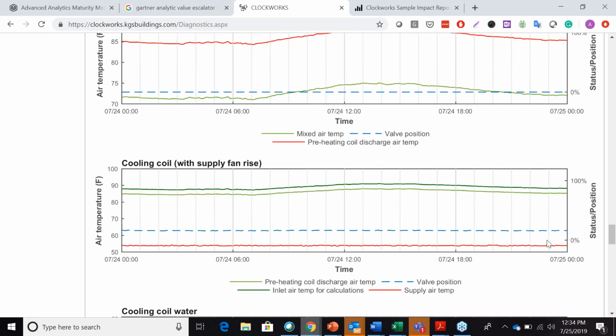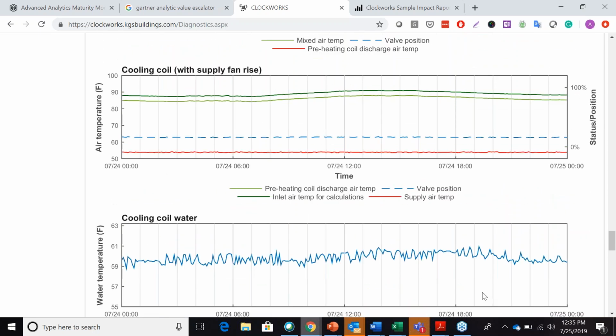On the next graph here, the cooling coil is opening. That's that blue dotted line again. It's doing exactly what it should do, bringing the air temp from the 80s down to a nice, perfectly comfortable temperature of 54 degrees. So if you look at this example, no building automation alarm is going to go off here because we're still meeting our set point. But in order to get it there, we're doing a lot of heating and doing a lot of cooling unnecessarily.